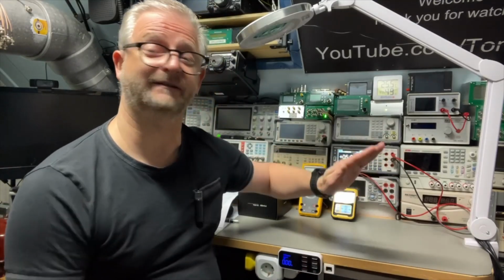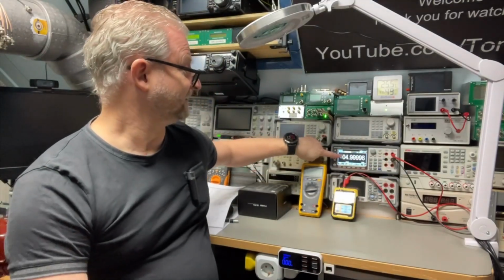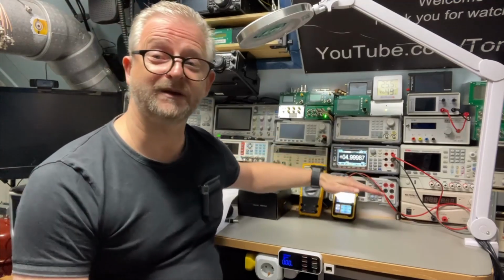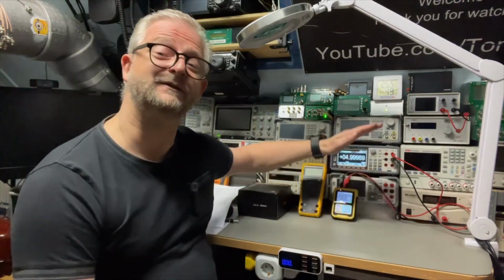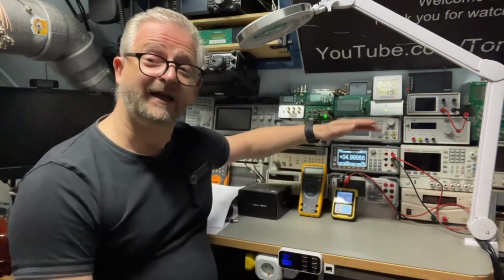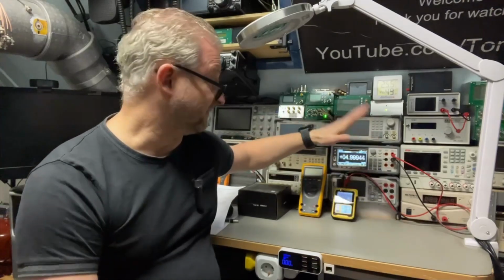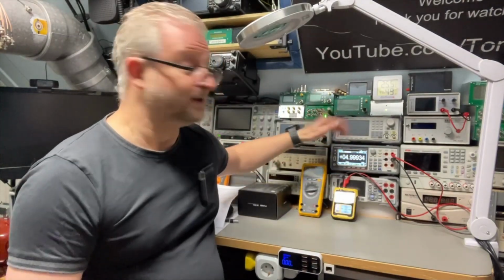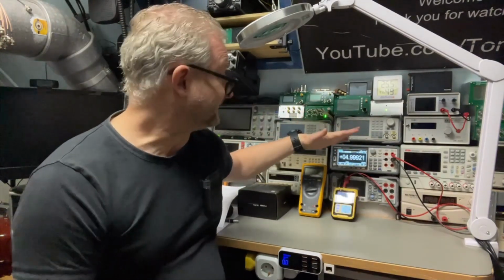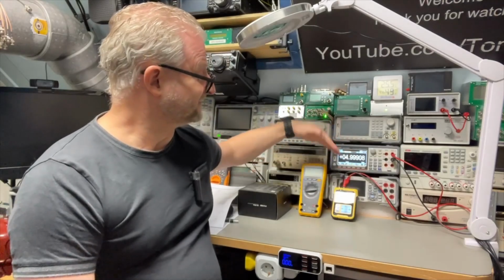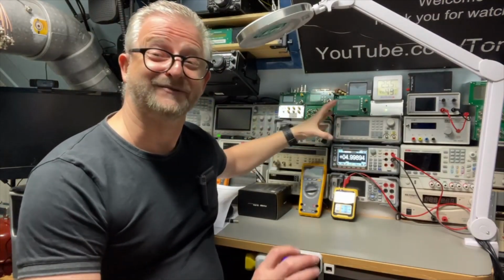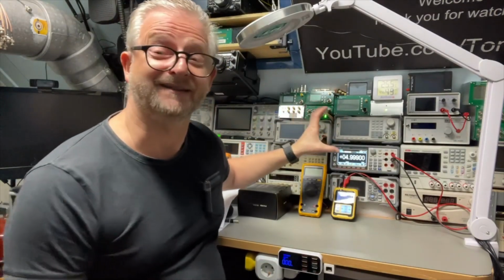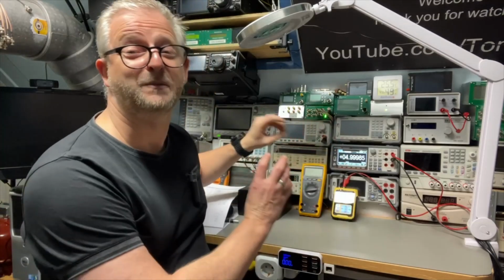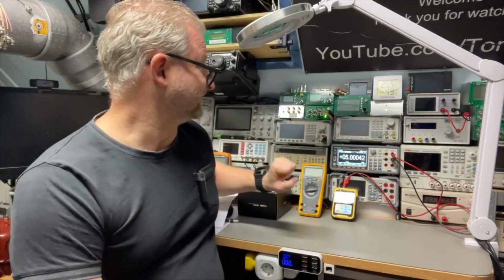It is interesting to see how it is trying to stabilize itself. Then it is 5, then it goes fractionally below, notices it is too low, goes up, goes down, constantly adjusting itself. And it actually works well, because doing that it stays within specifications. But you can see it's not a real calibrator, because it's also not designed for that purpose - it's really a debugging device for processors.